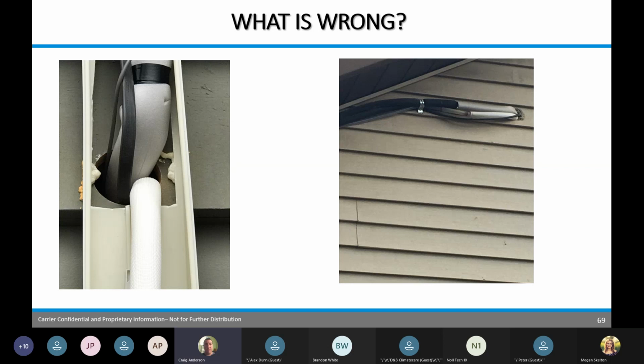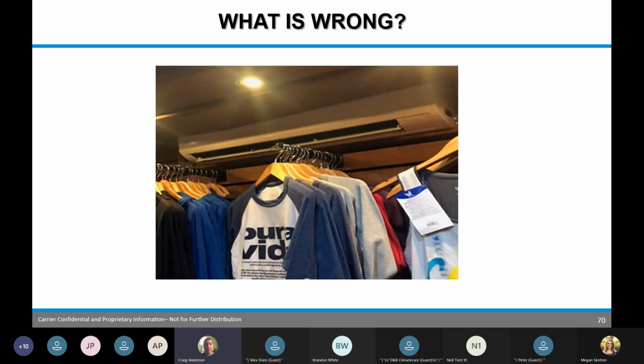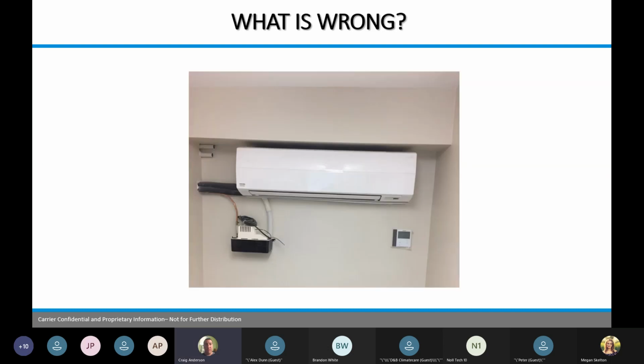This one here is half up in the T-bar ceiling and halfway down. We're not getting proper airflow to that unit. It's not going to run properly. This one here, nice clean install, looks fantastic. They have it tight to the ceiling. That's where your return air is being drawn in. We're restricting the return air.